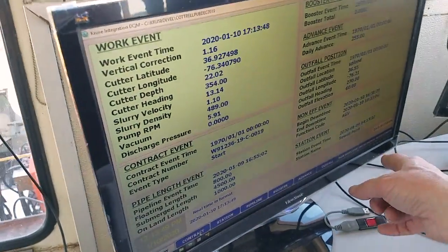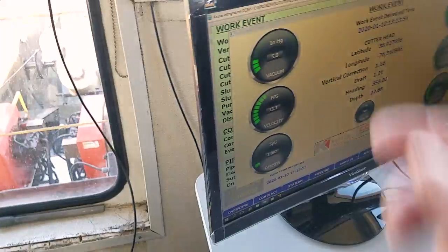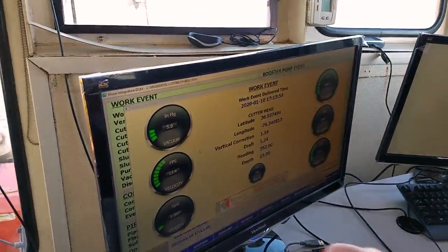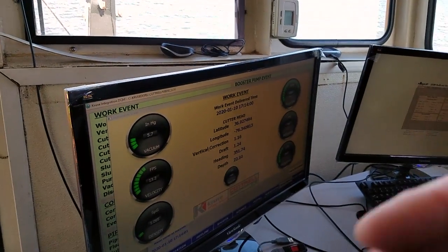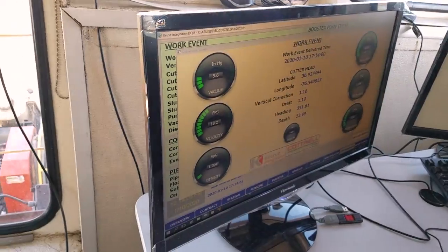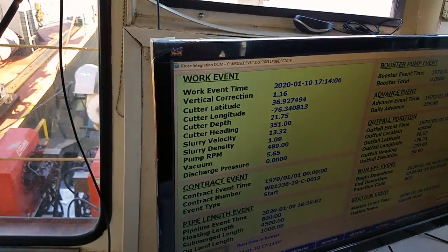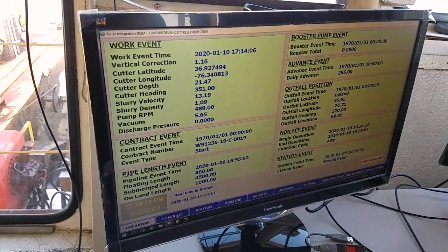If you go to the instrument screen, that's live data, all right? These are the ones that we send every 6 seconds. 6 second lag. Yeah, it's an average. What I do in the PLC per their spec is I average the instrumentation for those 6 seconds and then send them an average of that last 6 seconds. So it's a true stream just with a built-in 6 second delay. That's correct. Okay. Yeah, it's a JSON string.